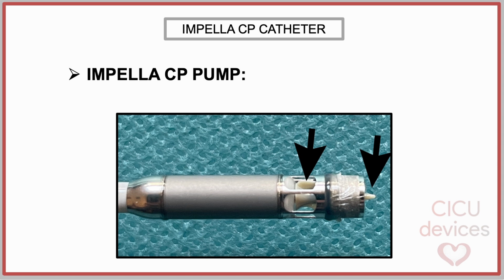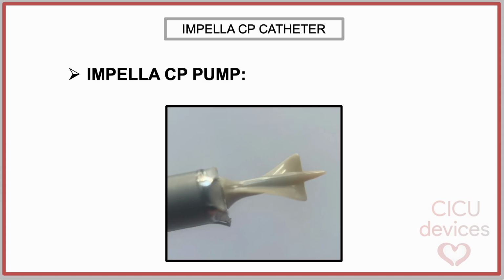Impella CP Pump. The Impella CP Pump consists of an impeller that functions as an axial pump. This impeller is enclosed within the pump housing. The Impella pump consists of a central conical hub, into which two blades are inserted, designed in a helical shape around the hub. These are the measurements of the impeller: 10 mm in length and 3 mm in diameter.